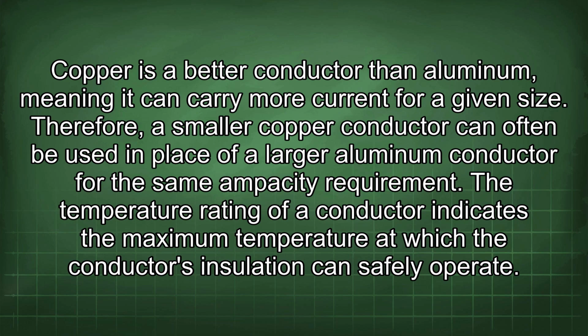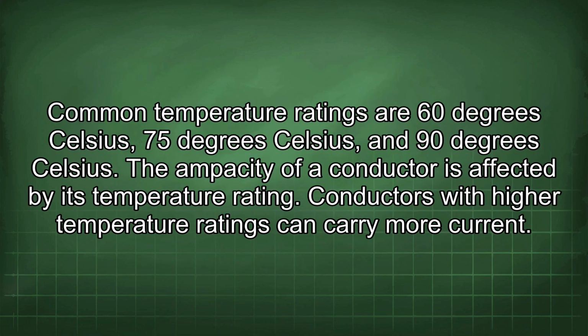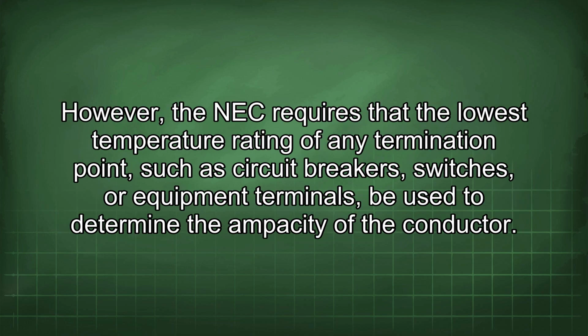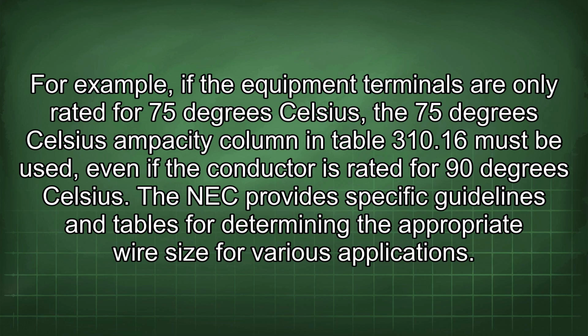for the same ampacity requirement. The temperature rating of a conductor indicates the maximum temperature at which the conductor's insulation can safely operate. Common temperature ratings are 60 degrees Celsius, 75 degrees Celsius, and 90 degrees Celsius. The ampacity of a conductor is affected by its temperature rating. Conductors with higher temperature ratings can carry more current. However, the NEC requires that the lowest temperature rating of any termination point, such as circuit breakers, switches, or equipment terminals, be used to determine the ampacity of the conductor. For example, if the equipment terminals are only rated for 75 degrees Celsius, the 75 degrees Celsius ampacity column in Table 310.16 must be used, even if the conductor is rated for 90 degrees Celsius.